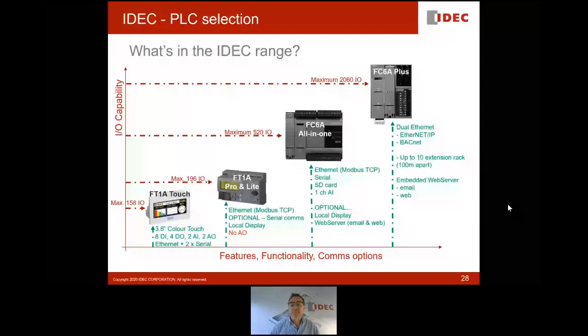So back to our example, the one where we had our 54 digital in, 39 digital out, 3 AI, 2 AO, PID, and then Modbus to a drive and Ethernet to a panel. For this solution, just to give you an idea, I've selected the FC6A all-in-one type because it provides us all the communications that we need and also meets the I/O requirements.